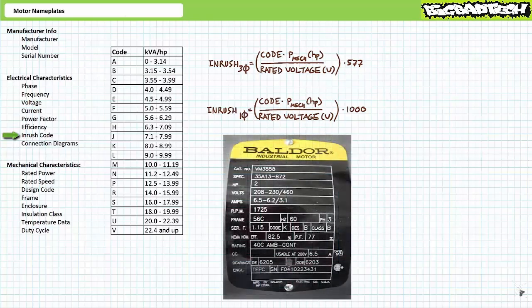Consider the previous 2 horsepower motor rated for 460 volts in the high voltage configuration with code K. In the high voltage configuration, we know it draws 3.1 amps. If we just wanted a quick estimate about inrush, we could say it's going to draw roughly 6 times 3.1 amps, or roughly 18.6 amps. This is an okay estimate.